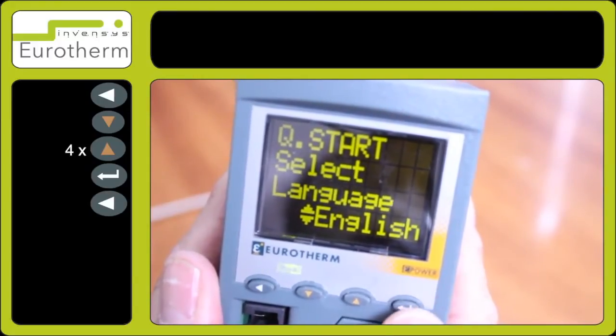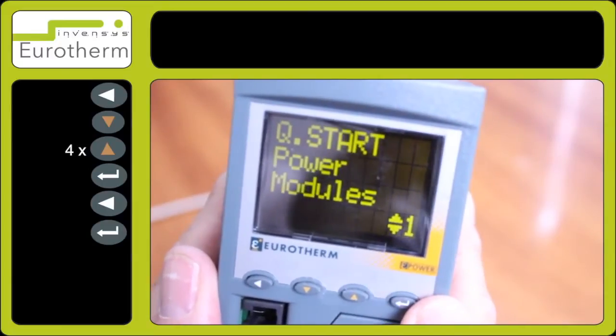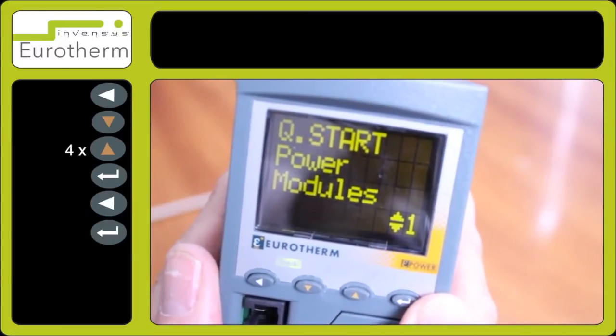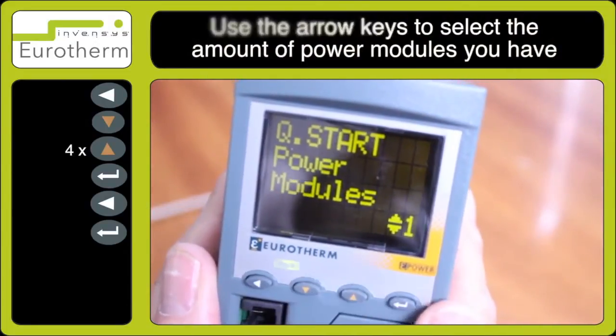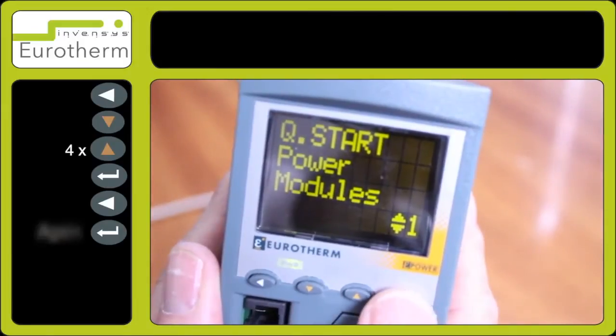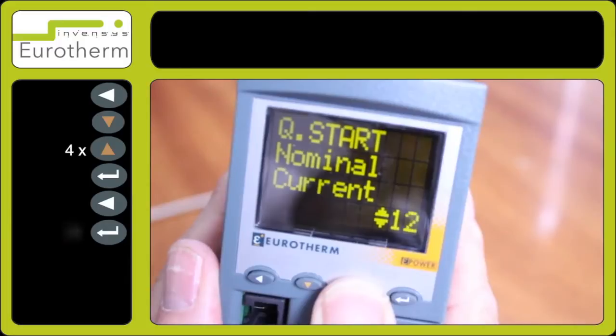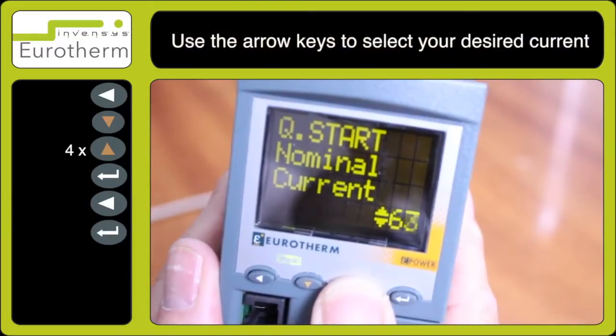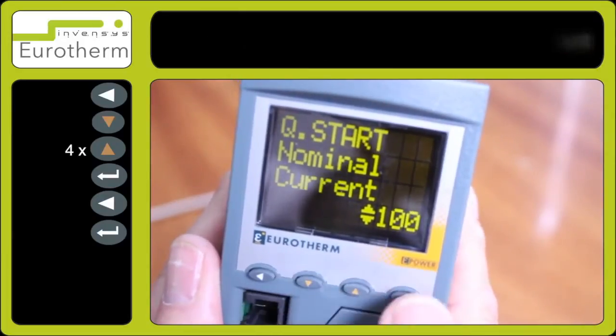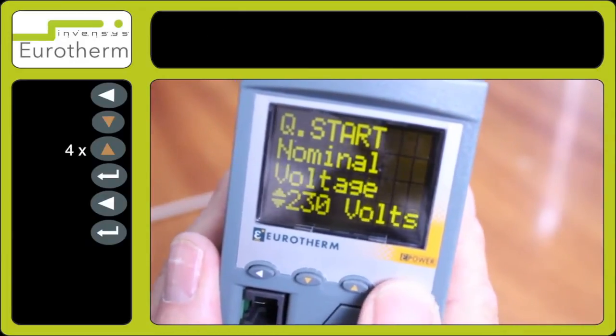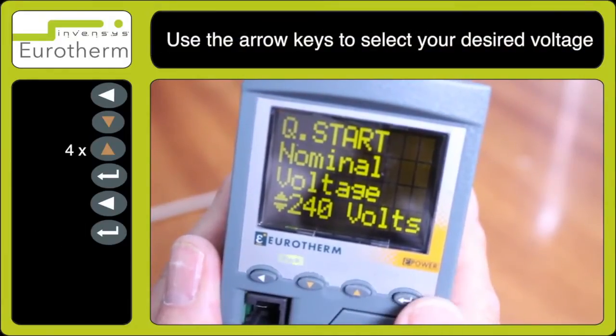You have now entered the quick start code. Select your language — in this case, English — and the number of power modules you have; in this case, one. Then select the current — I have selected 100 amps — and the voltage, selecting 230 or 240 volts.